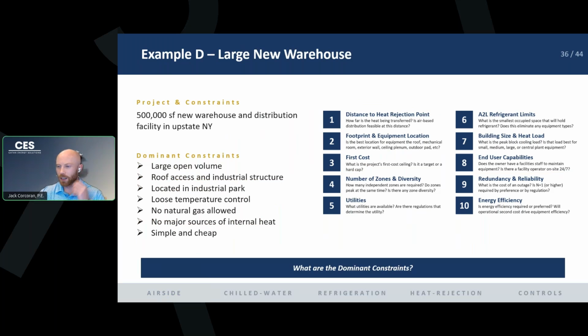So example D, a large new warehouse, right? We got a 500,000 square foot new warehouse and distribution facility in upstate New York. Our dominant constraints are that we got one large open volume space. There's plenty of roof access, and it's an industrial building, so there's lots of structure and it's beefed up. So sticking a unit on the roof is not going to require extra precautions. It's located in an industrial park. Maybe you don't care how it looks on the roof, and you can be as loud as you want.